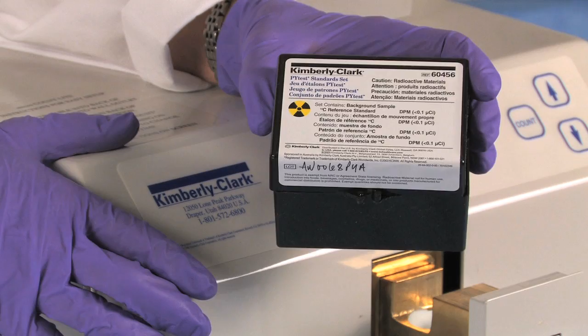It's important that you do that once a day at the same time. This machine will reset its internal calibration every 24 hours. Insert the background sample and count it. Remove the background sample and insert the C14 sample and count it. If anything is not calibrated, we will have an error message here that tells you that it did not calibrate. There could be a number of factors for causing the machine not to calibrate. One, the machine may not calibrate if it hasn't been 24 hours since the previous calibration.